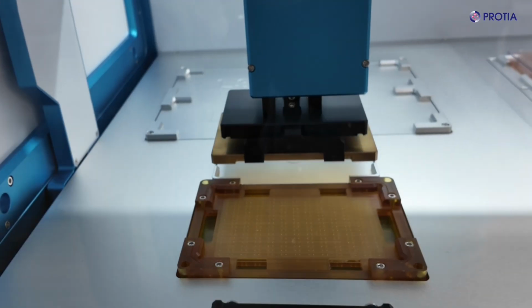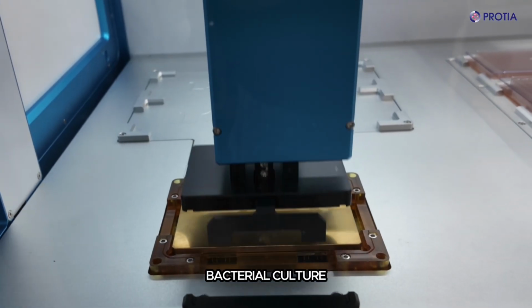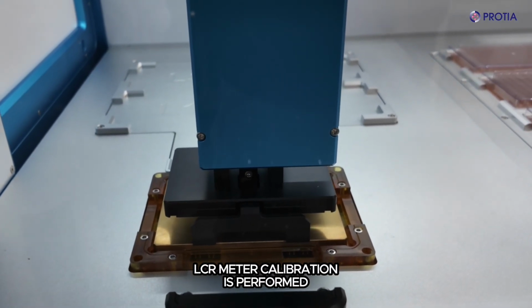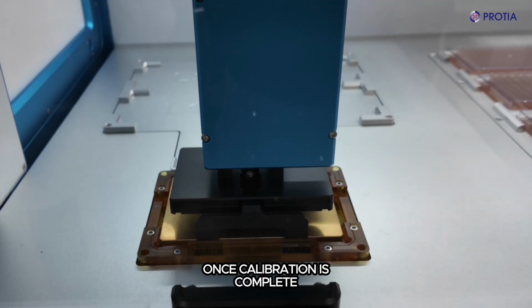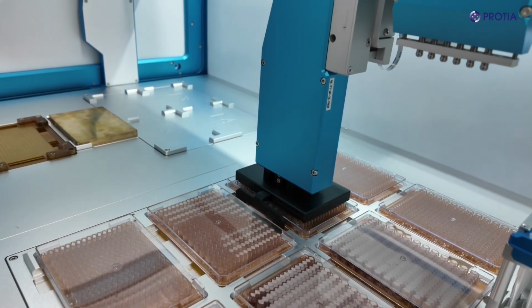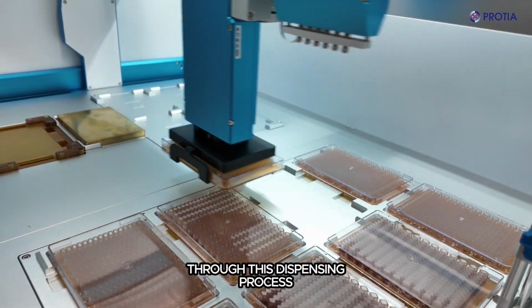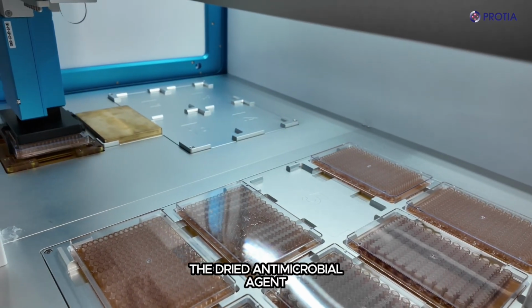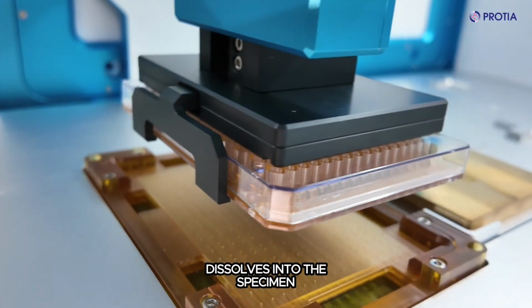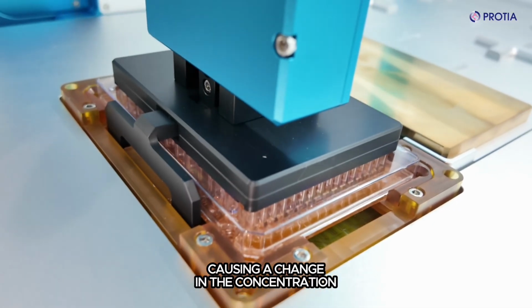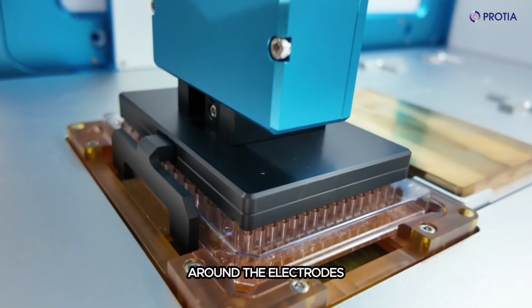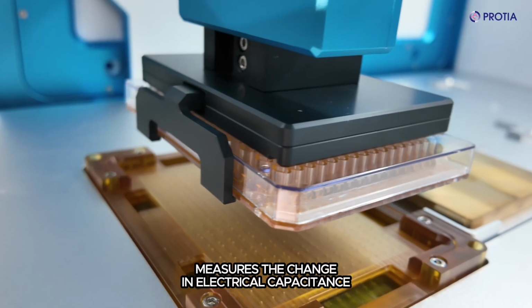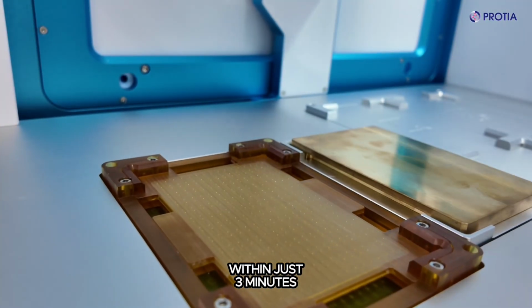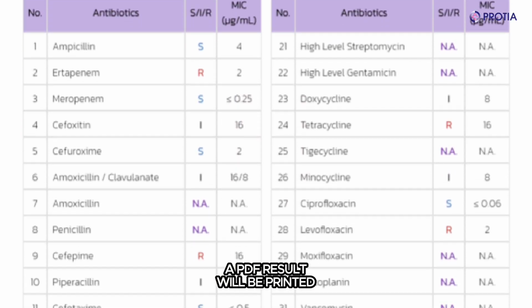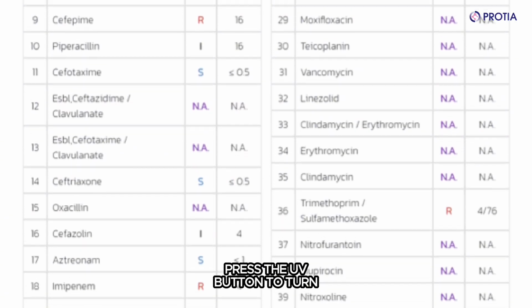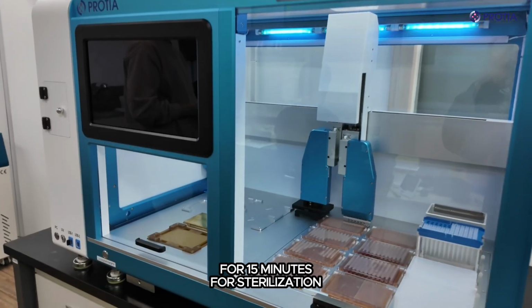To accurately calculate the exact change in the bacterial culture, LCR meter calibration is performed. Once calibration is complete, the equipment will measure the electrical capacitance of each plate. Through this dispensing process, the dried antimicrobial agent dissolves into the specimen, causing a change in the concentration of microorganisms around the electrodes. The equipment measures the change in electrical capacitance in just 3 minutes. When it's done, a PDF result will be printed. Once completed, press the UV button to turn on the UV lamp for 15 minutes for sterilization.